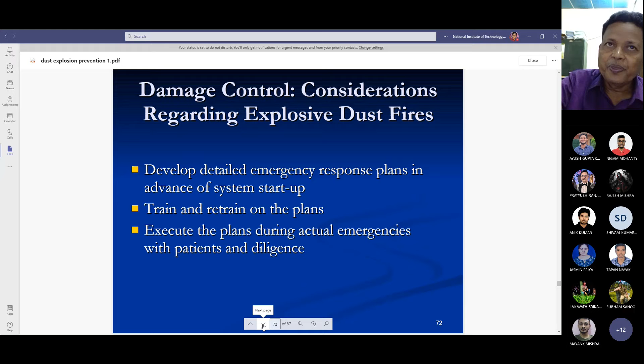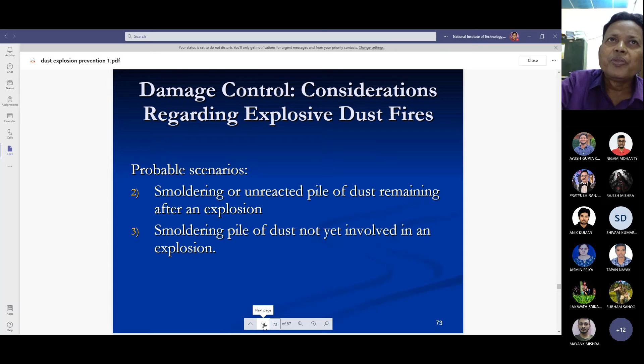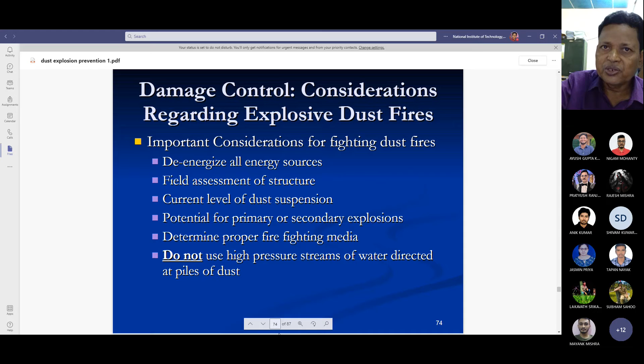And a probable scenario in case of coal dust explosion is smoldering or unreacted pile of dust remaining after an explosion. Smoldering pile of dust not yet involved in an explosion. Damage control mechanisms, like important considerations for fighting dust fires. For that purpose, you have to de-energize all energy sources so that ignition sources can be controlled, field assessment of the structure, current level of dust suspension, potential for primary or secondary explosions, determine proper firefighting media. Do not use high pressure streams of water directed at piles of dust.